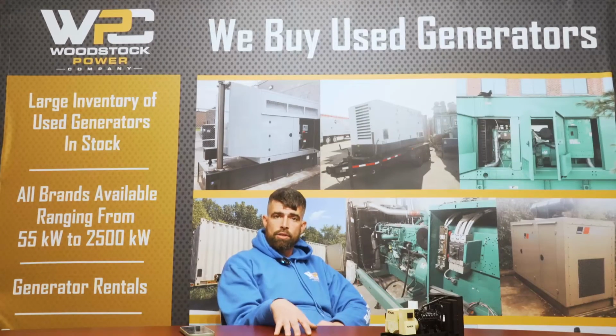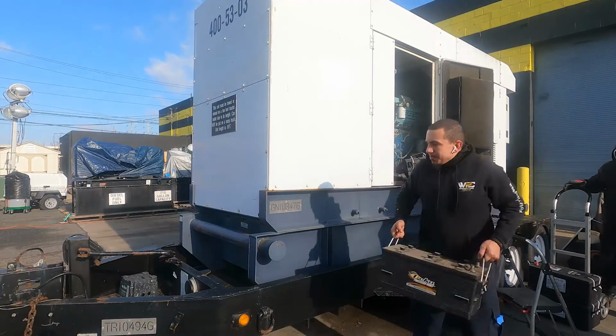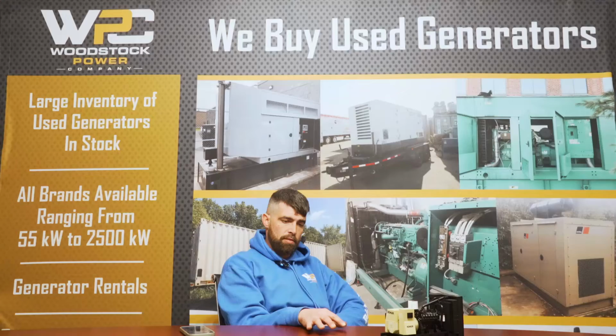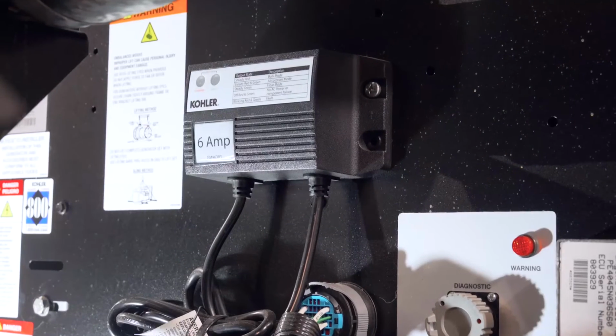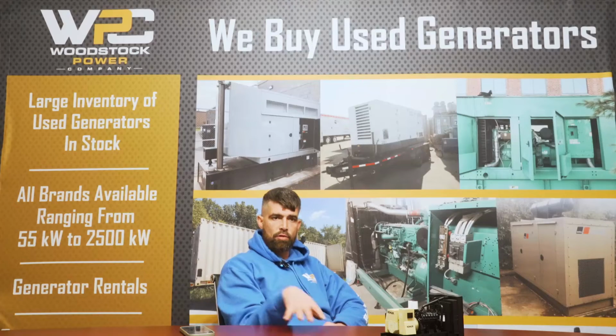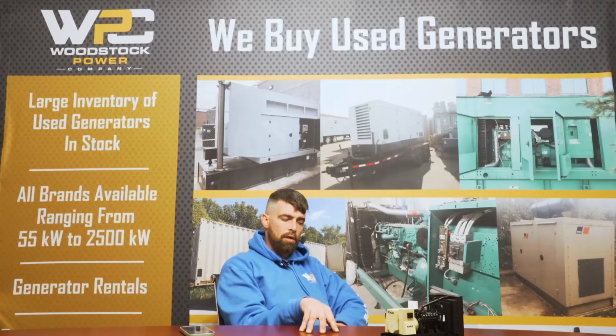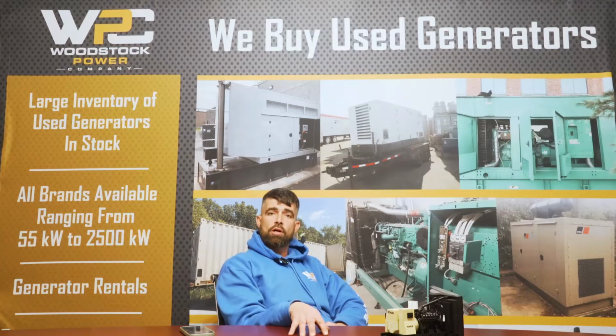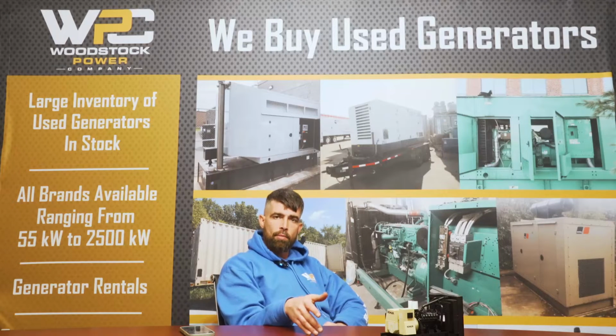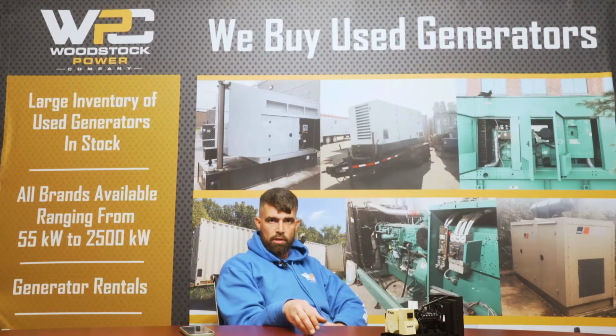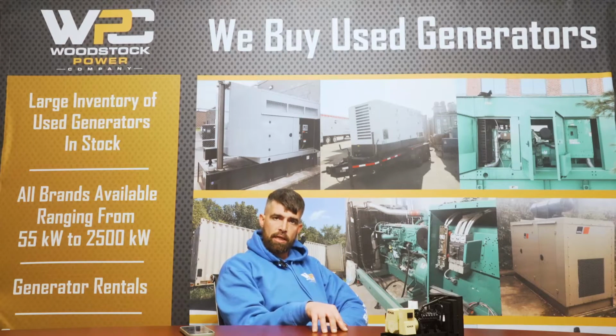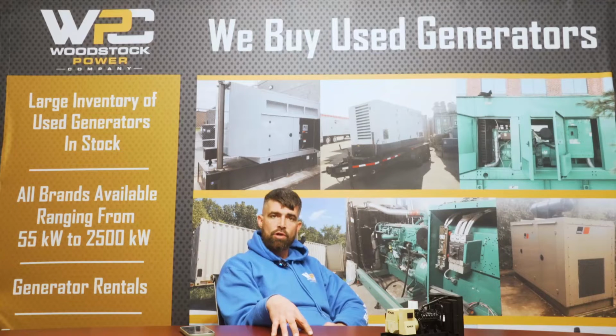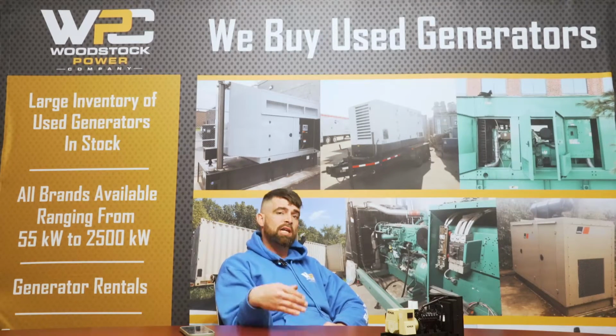Just like anything else, generators have a starter that works on batteries. Batteries are very important to maintain the starter, the control panel, the block heaters, the battery chargers, everything else that goes into the machine on low voltage and to start the generator. Batteries not being charged or having low voltage is the number one cause of failure for generators to start. Always make sure that your batteries are charged, that your battery charger is connected and operating. If you don't have a battery charger, disconnect the negative and the positive off of your batteries when you're not using the generator. Connect them back again when you are.